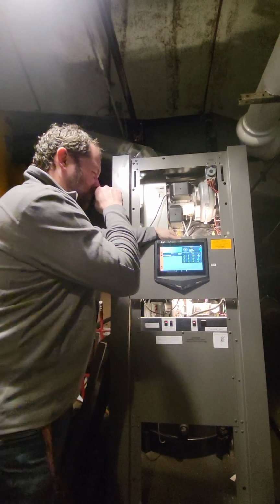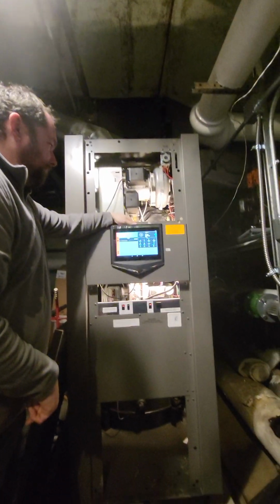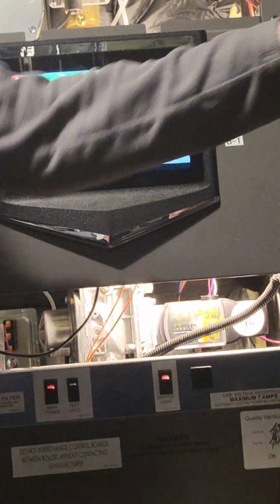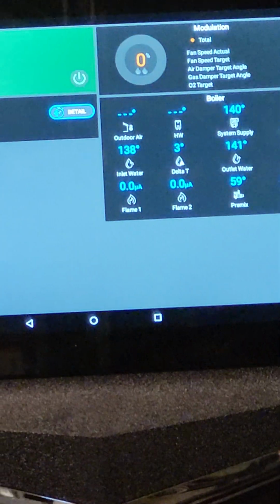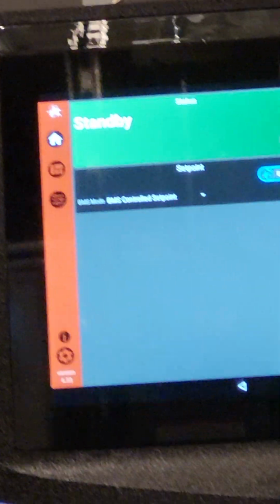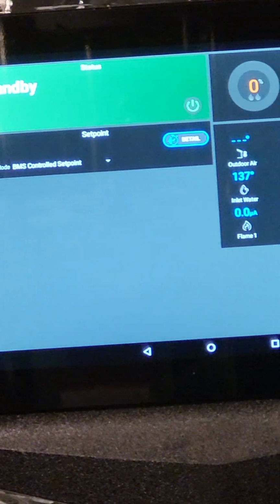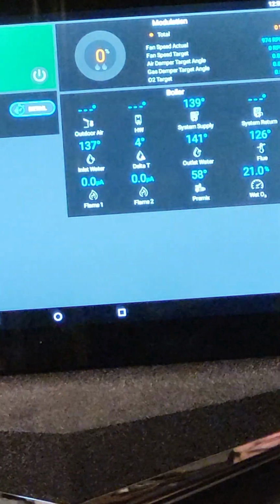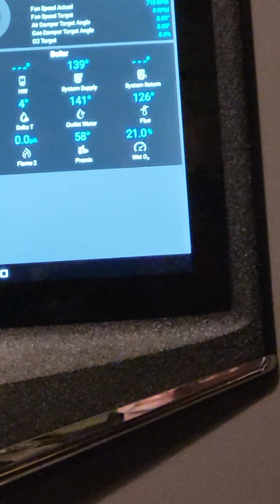So back to our main screen again. Now, what I was telling you guys before was not shutting the switch off. When it's not in use, he's not enabling the boiler, so there is no reason to shut this unit off. It will not run unless it goes into freeze protection. Nothing wrong with it sitting here ready to go. I would not recommend shutting them off, only if you're working on the electrics or something like that. Other than that, leave it on.